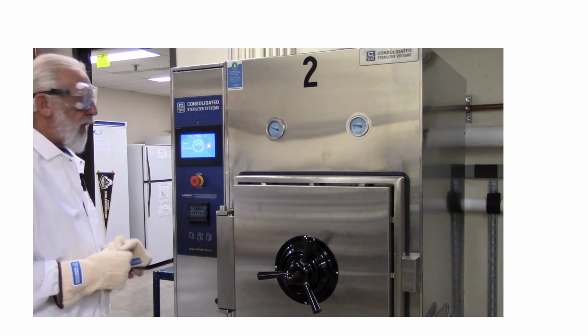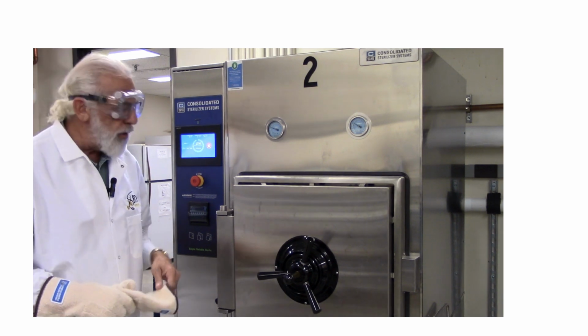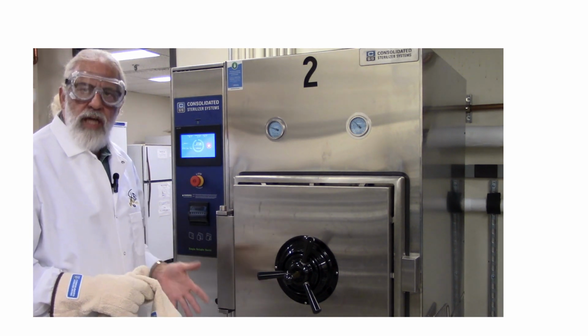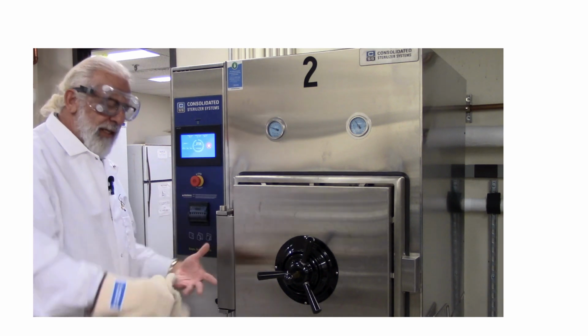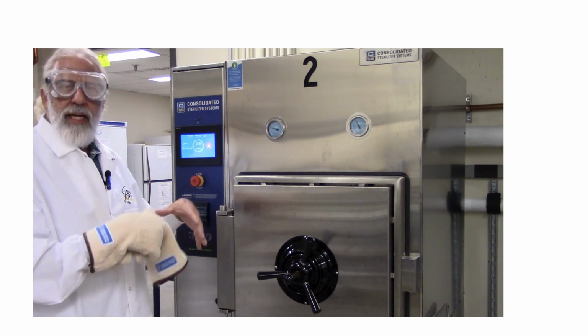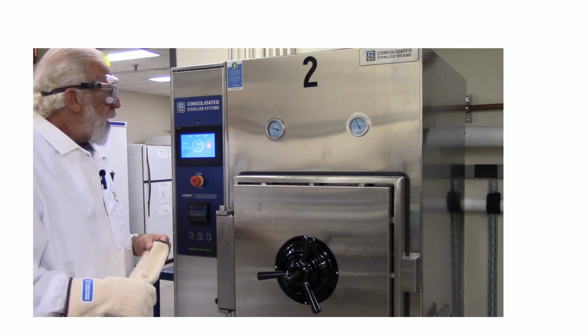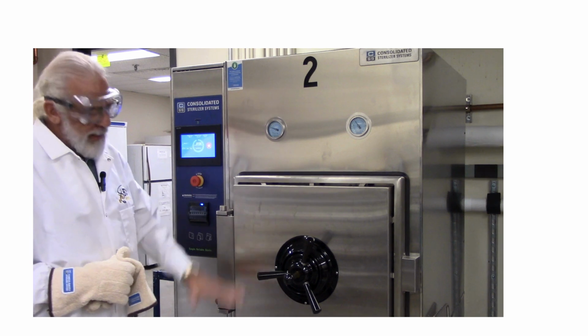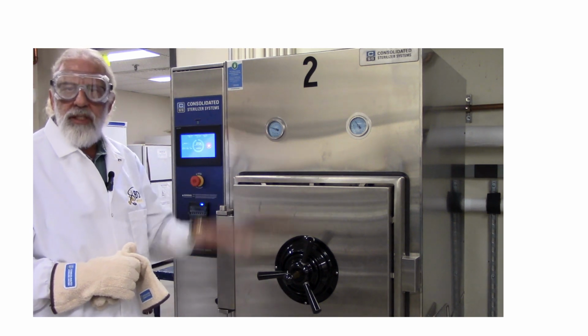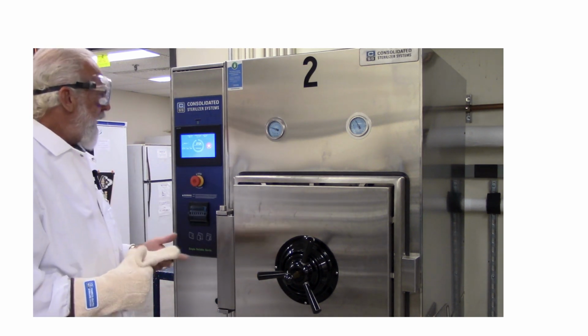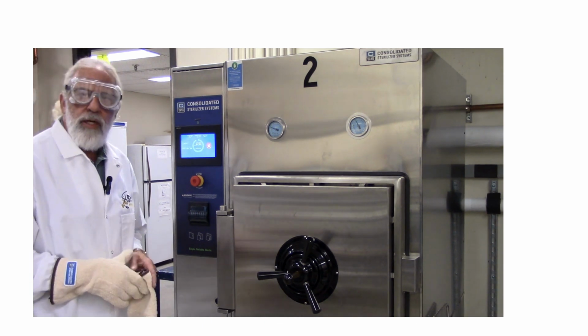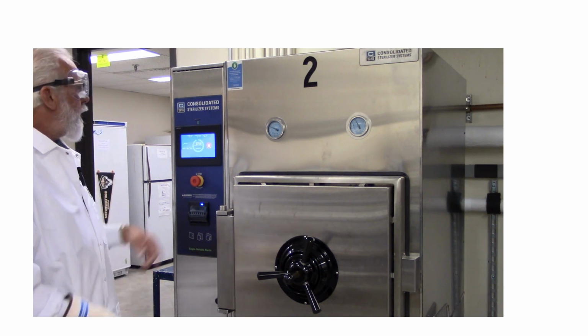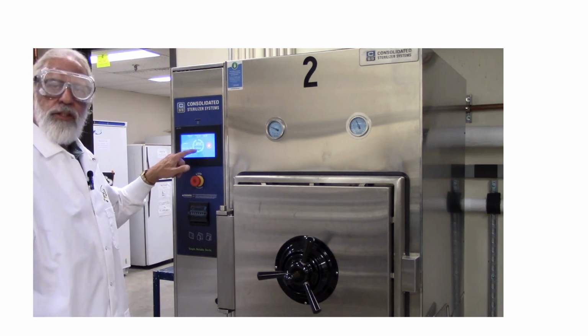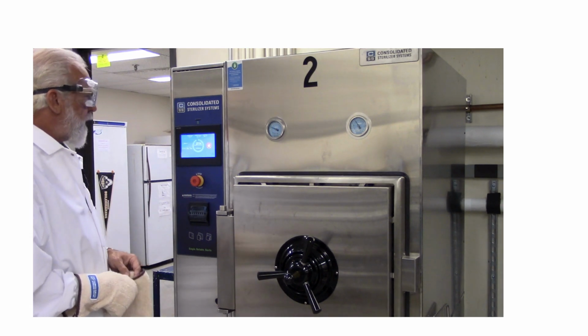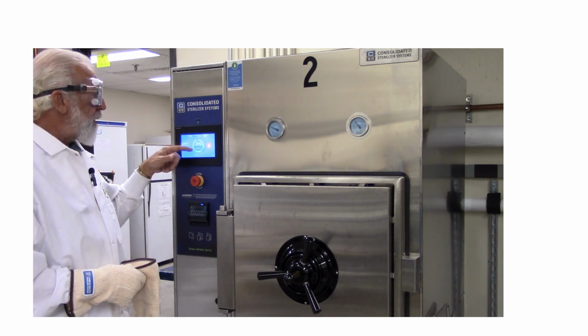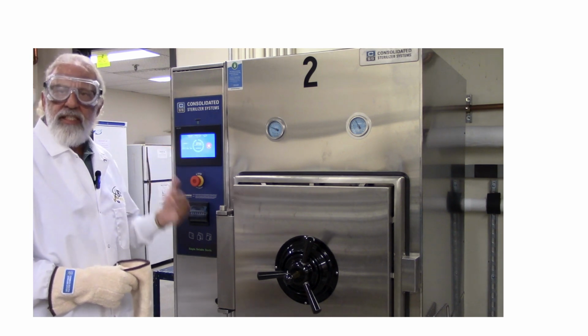The first thing the autoclave will do is purge the chamber of all air that's inside of it. It wants to get rid of the air inside of the pan, inside of anything that would be in the pan, and it'll do it by sucking air out and by forcing steam in. It usually takes a couple of minutes to run through the purge cycle. It indicates it as conditioning on the screen. This unit does a nice job of listing all the different stages that it's in.